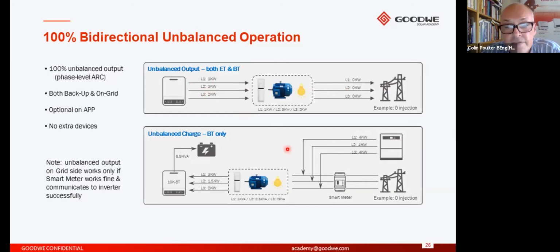At the bottom of the screen here, you can see an inverter generating 4 kilowatts on each phase. But we have different load requirements on the phases: on phase 1, 1 kilowatt, phase 2, in this example, 2.5 kilowatts, and on phase 3, 2 kilowatts. So you can see here, because we have the unbalanced charge capability, we are now picking up the individual excess power production on each of the phases, and that combined total output power can now be used to actually charge the battery. So I think that's a very useful feature to have.